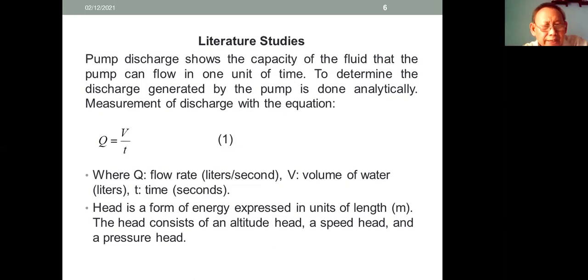Where Q is flow rate in liters per second, V is volume of water in liters, and T is time in unit seconds. Head is a form of energy expressed in units of length. The head consists of altitude head, speed head, and pressure head.